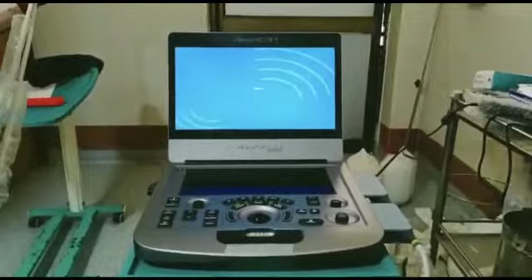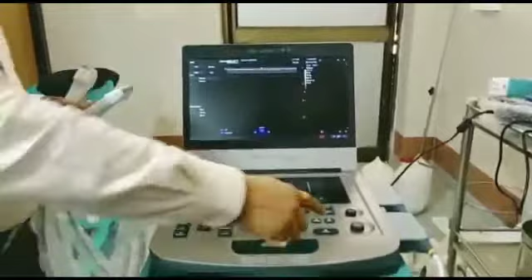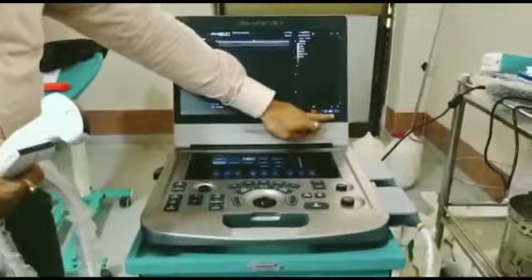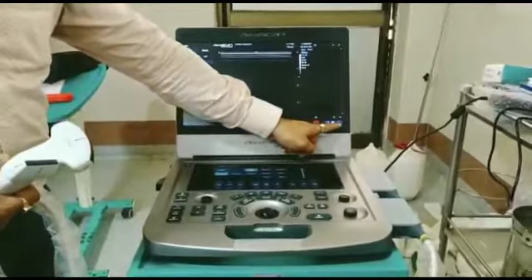Now machine is ready for scanning, so you just skip this one and machine is ready for scanning. So this machine has got two probe connector and inbuilt battery for 1 hour backup. Another battery slot is there for optional battery. One battery will give 1 hour battery backup. If you put another optional battery, that will give another 1 hour, means total 2 hours backup. The machine weight is only 4.5 kg.